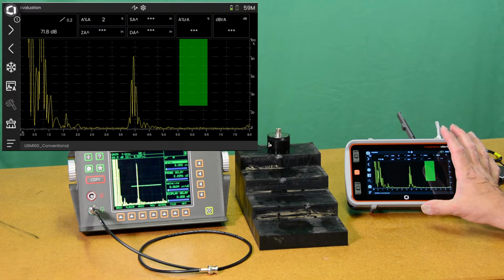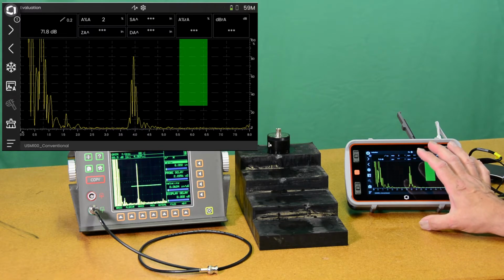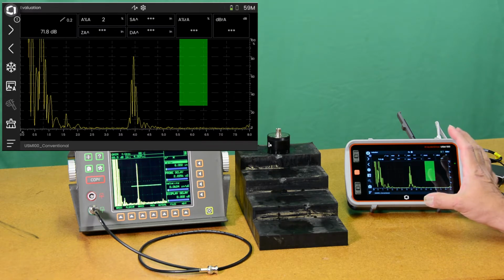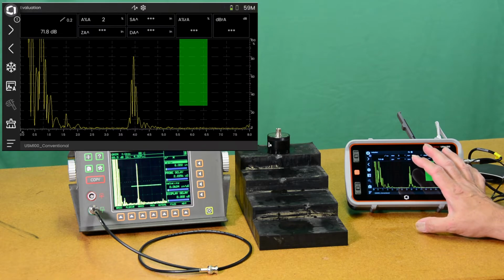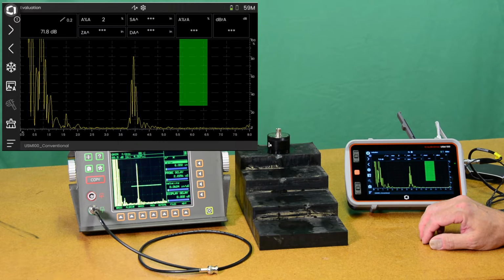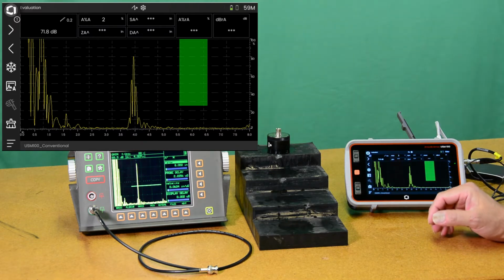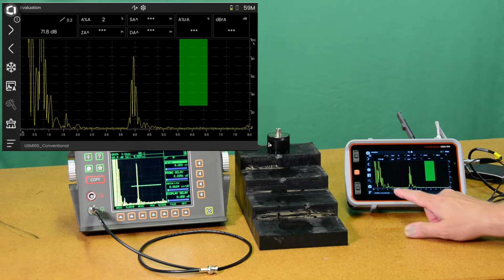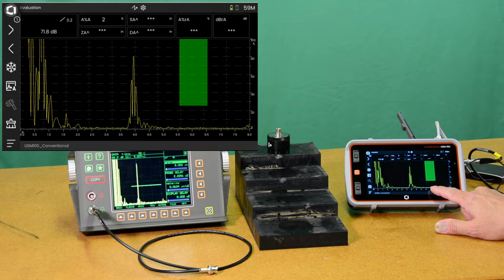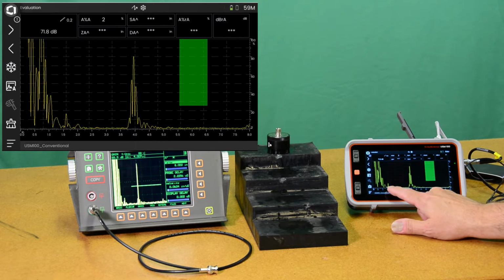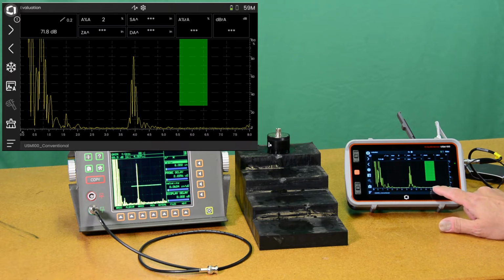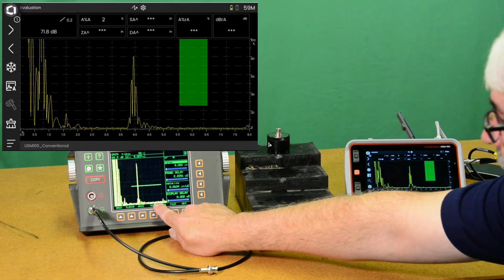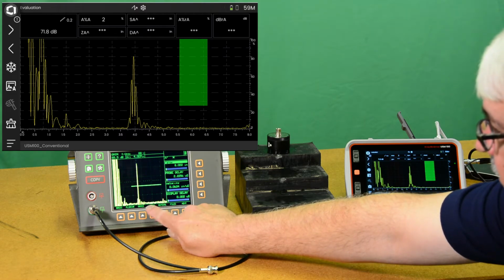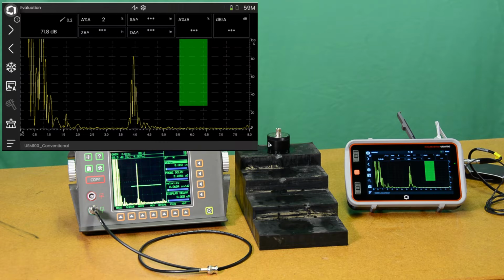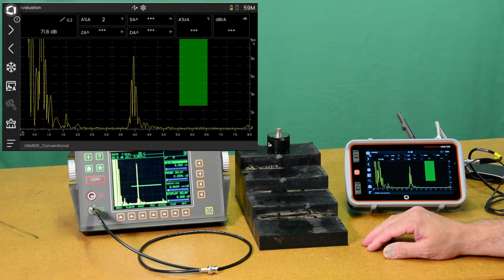That's coupled with a good low frequency filter in here. We have a filter optimized at 500 kilohertz. And that, coupled with the very quiet amplifier that's in this instrument to begin with, really shows off this particular application. So again, on the left, the USM60, on the right, the USM 100. You can see in the USM 100, our noise floor is lower. It's only a couple of percent screen height. We have some acoustic information up front here, but the basic noise floor of the instrument is still very quiet, down below 2 or 3%. Here in the USM60, you can see a higher noise floor. That's about 4 or 5%, a little higher, some of it peaking closer to 8 or 9%. So just overall quieter and making more efficient use of the probe.